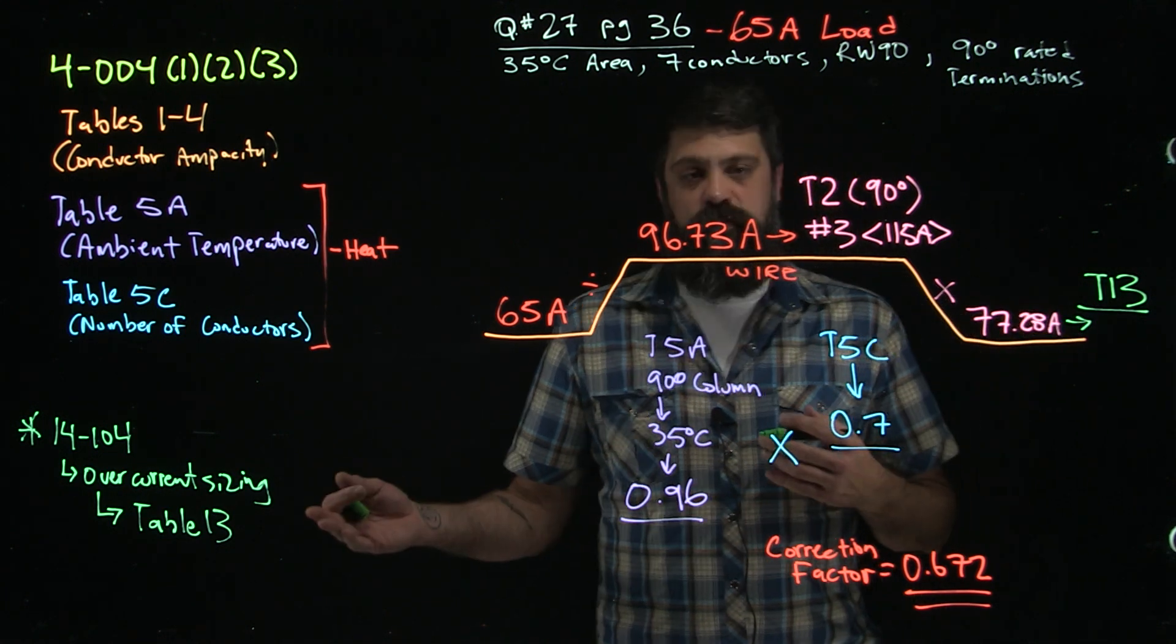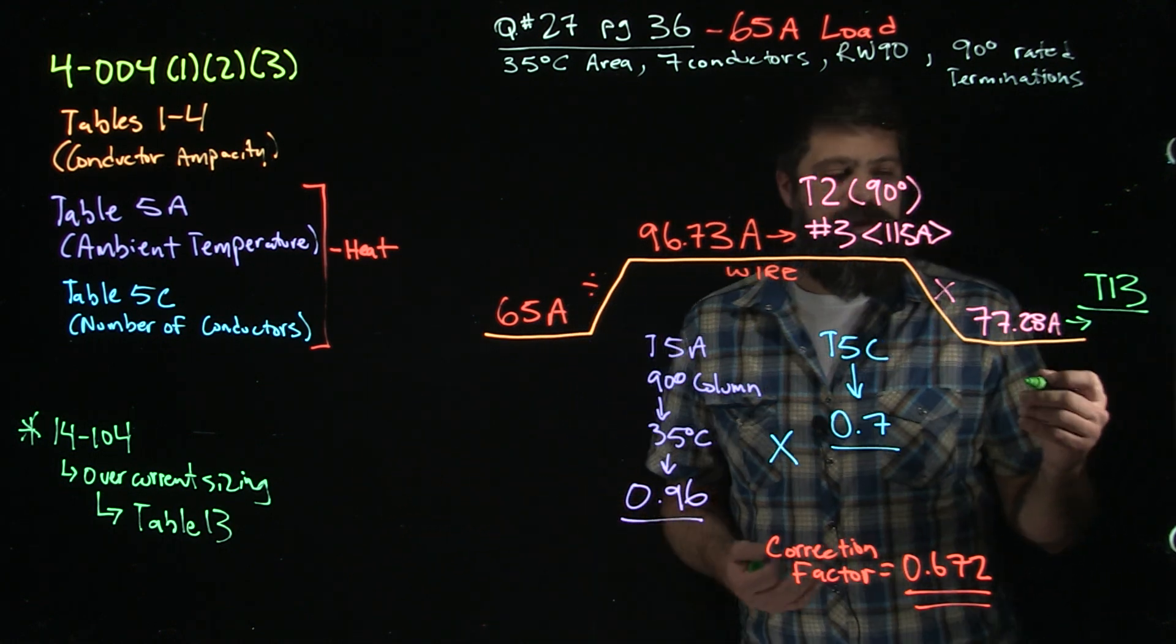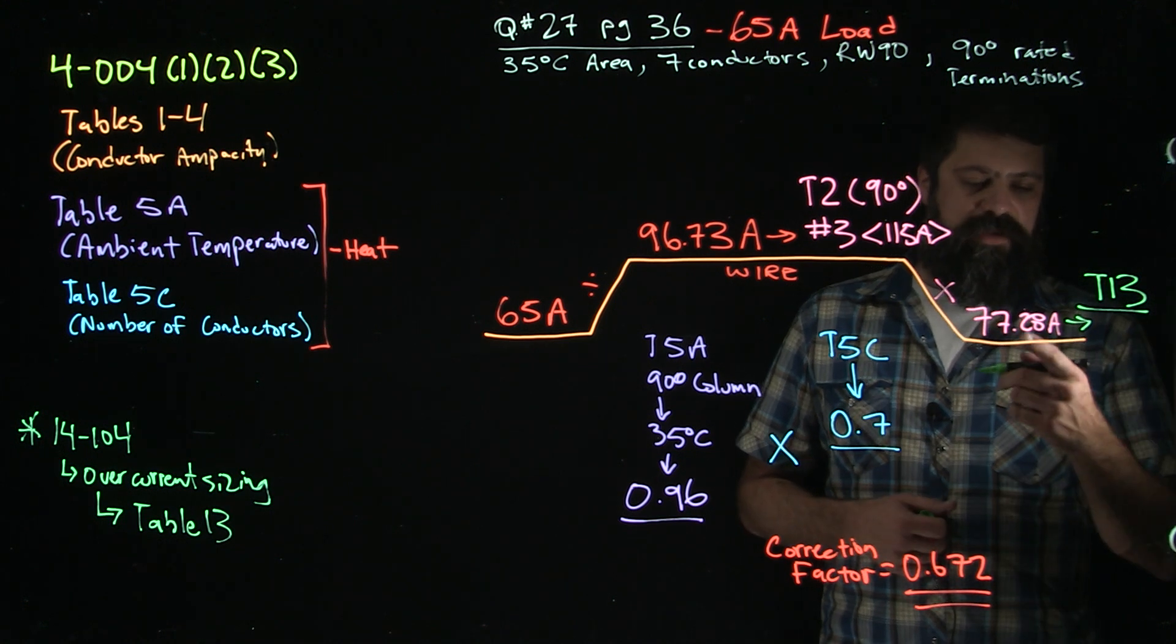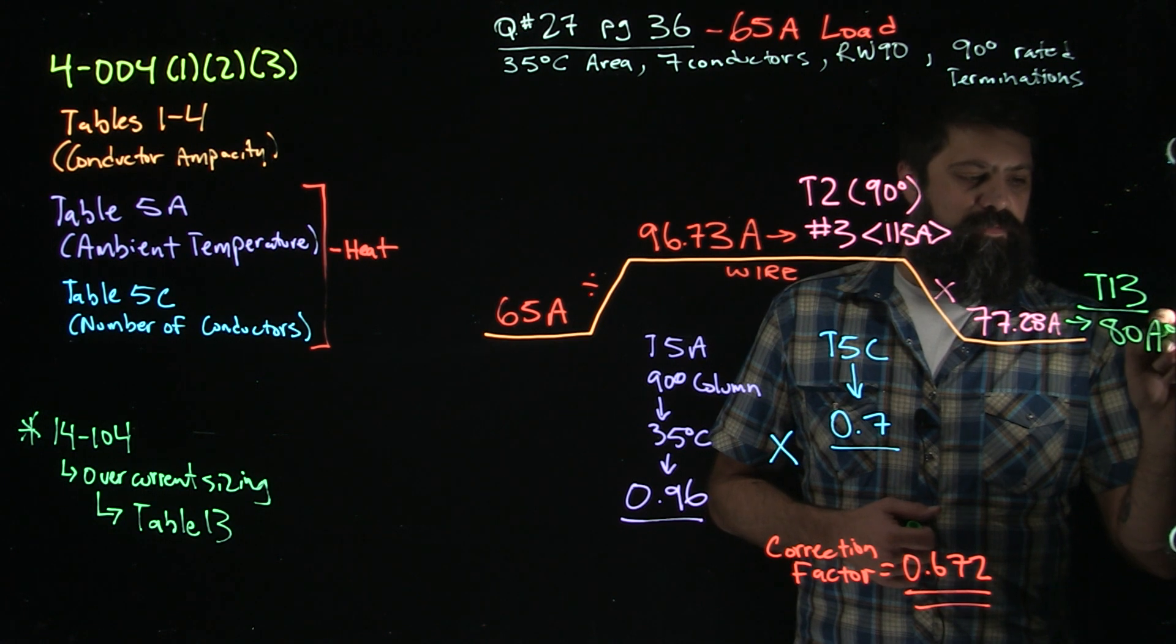Table 13, I need a breaker that's going to allow only 77.28 amps, but like the rule says, 14.104, it falls into that range. That's how Table 13 is arranged. So I can actually go up on this one. In that range, 77.28 amps, I'm going to pick an 80 amp overcurrent.